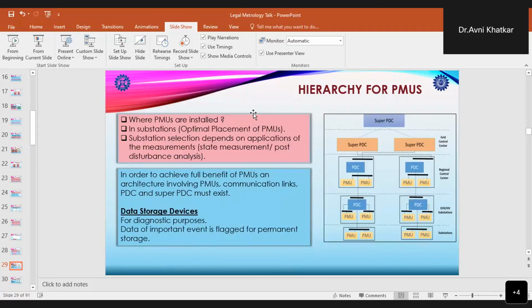And then the data from these PMUs, as per the deployment plan strategy, where these PMUs are to be installed. So these PMUs are to be installed as per the optimal placement strategy of the PMUs. That is, the substation selection will depend on the applications of the measurements, that is, whether it is required for state measurement or post-event analysis. So based on that, the PMUs will be installed in the grid. And in order to achieve the full benefit of the PMUs, an architecture which involves the PMUs, communication links, and PDCs and super PDCs must also exist.